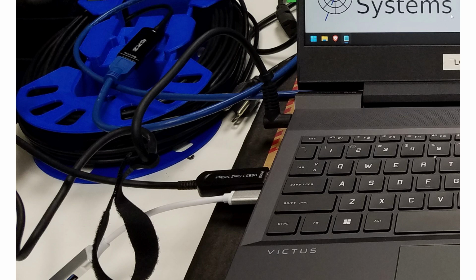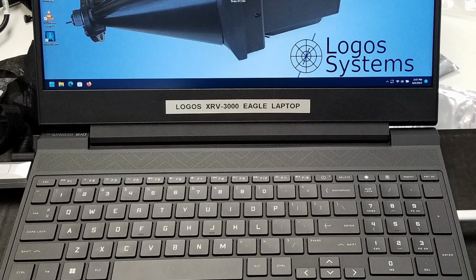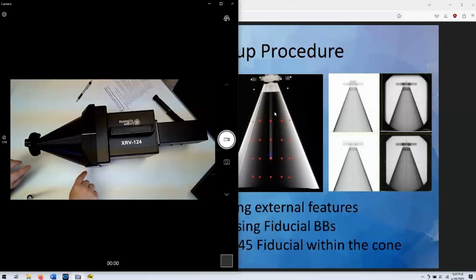A large proton treatment center with multiple treatment rooms should consider purchasing additional extender cables from Logos Systems for routing directly from the treatment room through the wall to the control room. Having dedicated treatment room cables will save 5 minutes of physicist time each time the XRV-124 is used because unspooling and respooling the cable is not necessary. This will also maximize treatment room uptime, especially if the XRV-124 is used for daily diagnostics.